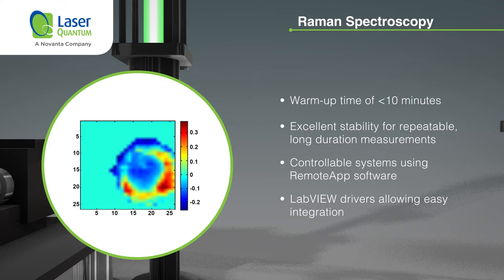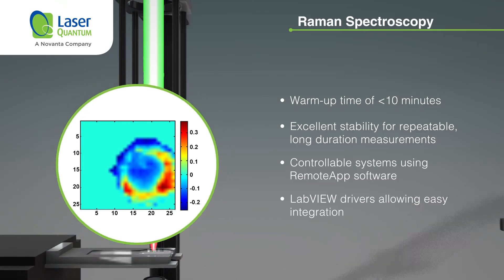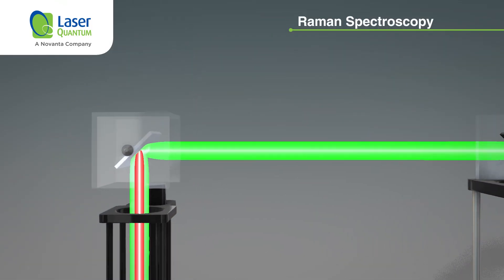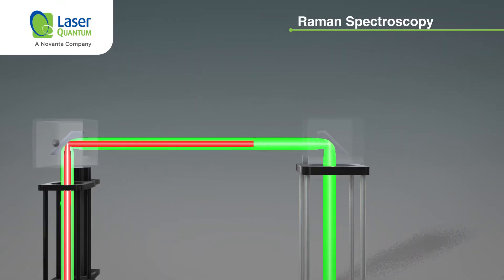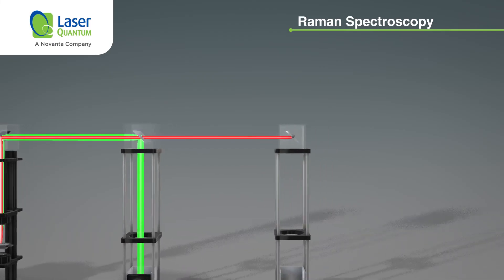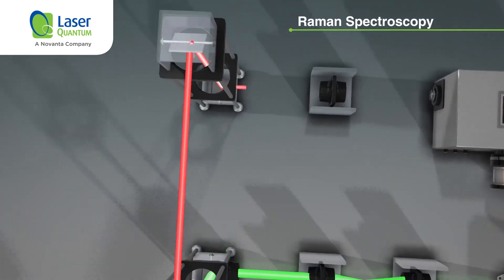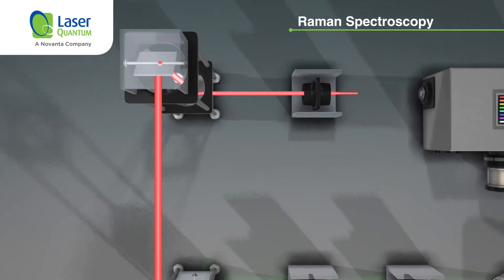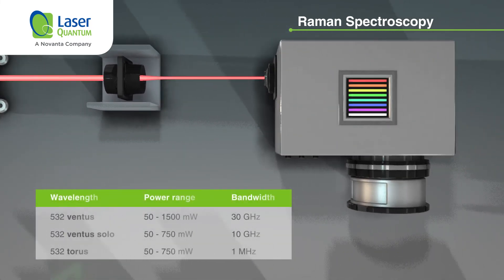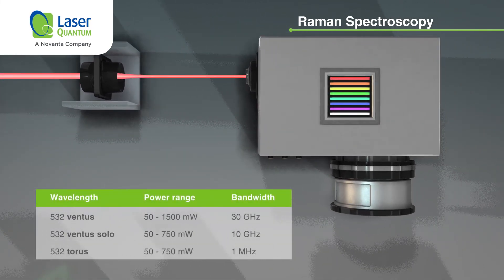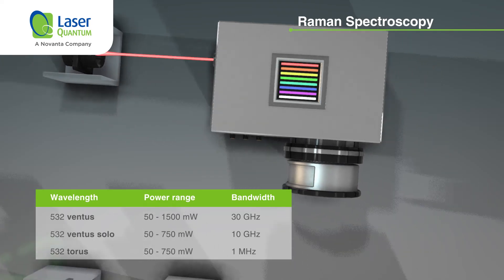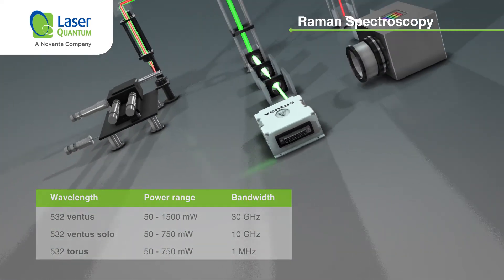For Raman mapping studies, excellent pointing stability across the range is ideal for free-space coupling to a microscope, with minimal drift over extended timescales. The 30 gigahertz bandwidth of the Ventus 532 is sufficient for the majority of Raman studies; however, in cases where greater resolution is required, the Ventus Solo and Torus offer narrower bandwidths.